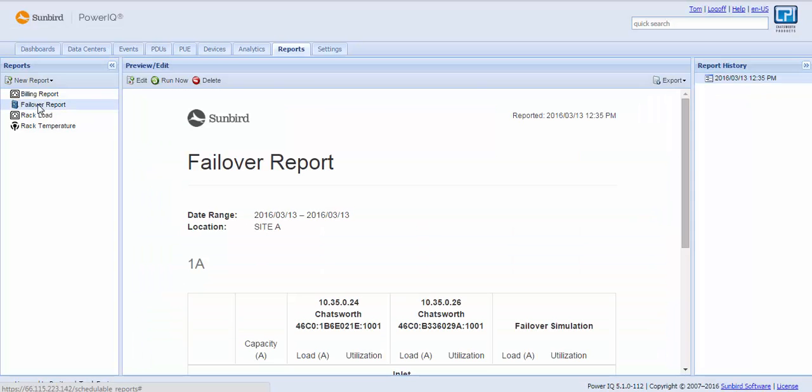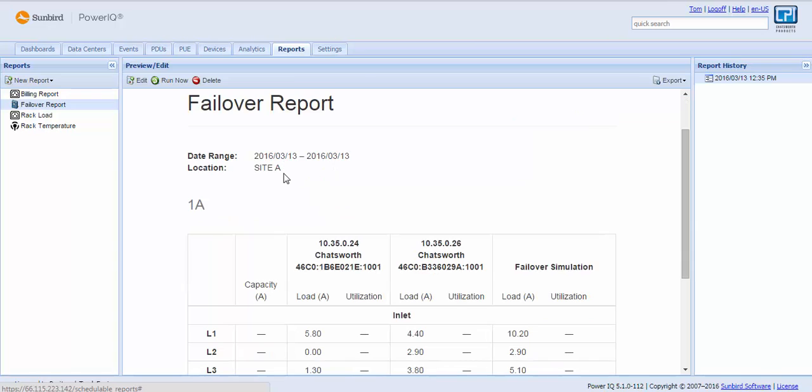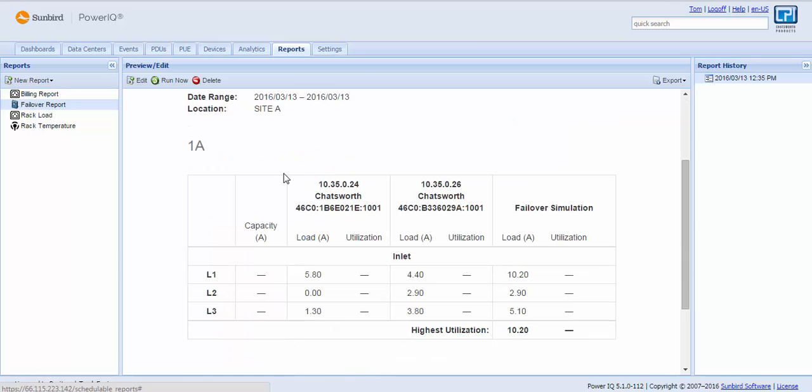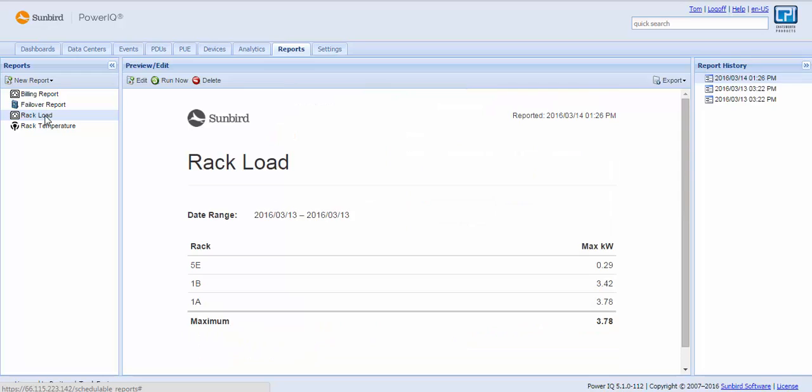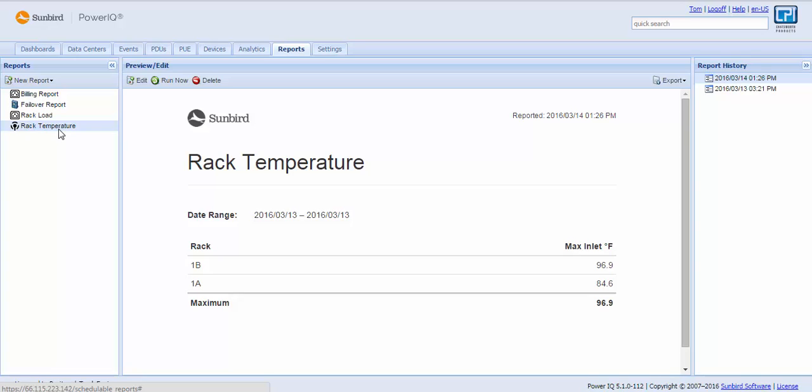We have a specialized report called a failover report, which will give you a cabinet-by-cabinet view. In this particular cabinet 1A, I see the load of my three phases for each PDU. And then what would be the load if there was a failover? What would be the result? We can have other reports, such as load by rack, temperature by rack. And creating a new report is tremendously easy.